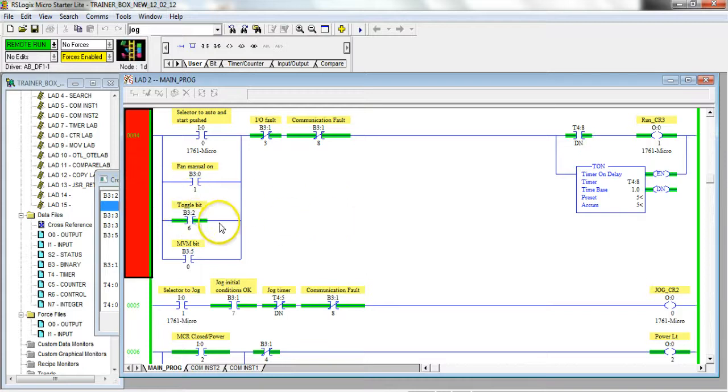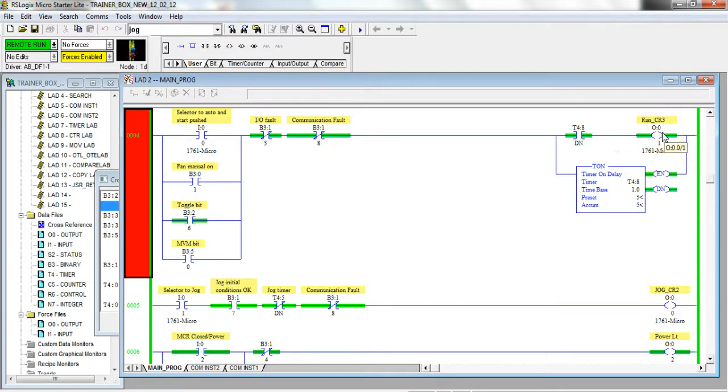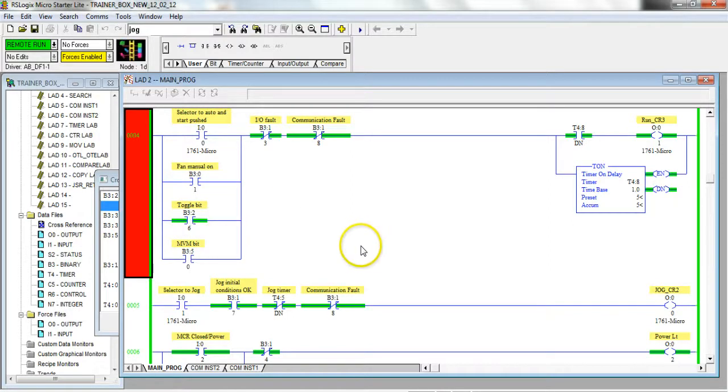There's that same toggle bit and it's tied in with this run control relay which actually starts my motor. So when I thought I was turning a light bulb on, I was in fact turning on a motor also.